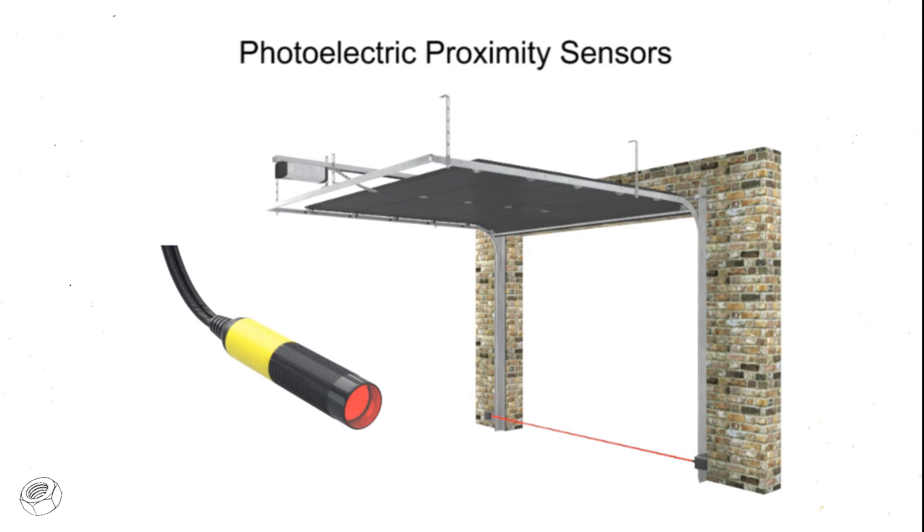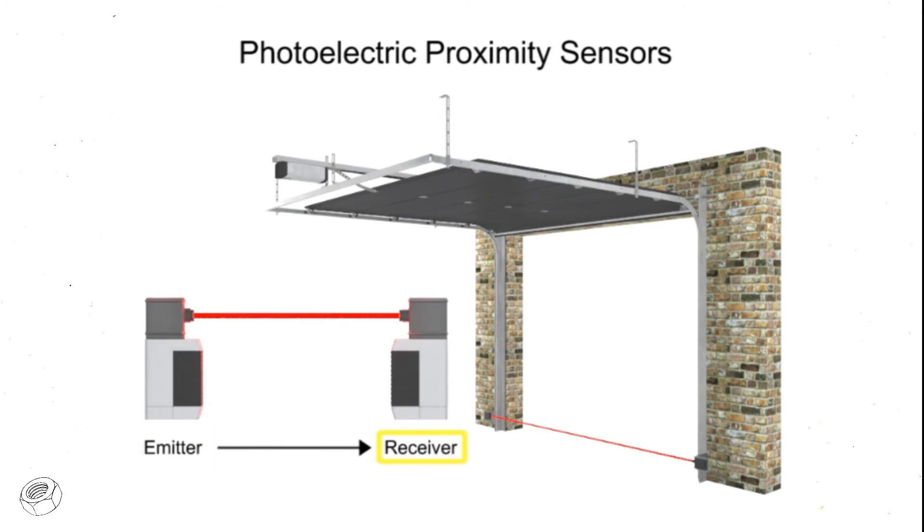Photoelectric sensors have the greatest detection range from 1 millimeter to 25 meters or more. They operate by the use of an emitter, which transmits a beam of light to the receiver. When the light is normally being received, it is known as a light-operated mode. When the absence of light is required, it is known as dark-operated mode.